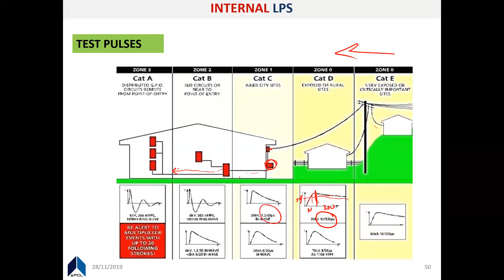If you have a lightning rod, there's a high chance of direct lightning strokes coming in, so you have to consider this high impulse value. Otherwise, only the maximum follow-up currents need to be considered. So if you have a lightning arrestor, you shall definitely go with type 1 plus other SPDs all along your installation - that's the basic concept.